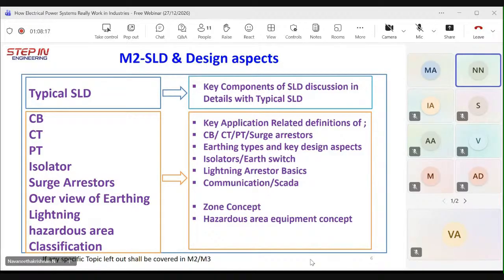Say for example, class P is applied for non-differential protection. Why class PS? Class PS is very specific to differential protection. Why we have to specify knee point voltage for differential protection. So those aspects we will cover in CT, and we will talk about CT, PT class and standard PT nomenclatures. And we will talk about isolator duties, what are the types of duties used, mechanical duty, electrical duty, we'll discuss in isolators.